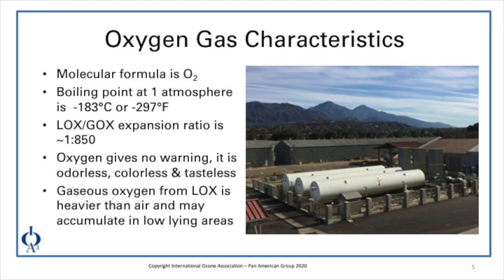The oxygen gas characteristics include that the molecular formula of oxygen is O2. It has a boiling point at one atmosphere of negative 183 degrees C or negative 297 degrees Fahrenheit. The liquid oxygen to gaseous oxygen expansion ratio is approximately 1 to 850. Oxygen gives no warning in that it is odorless, colorless, and tasteless. Gaseous oxygen from liquid oxygen is heavier than air and may accumulate in low-lying areas.